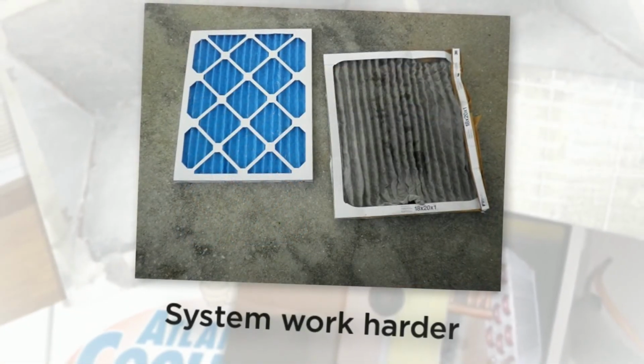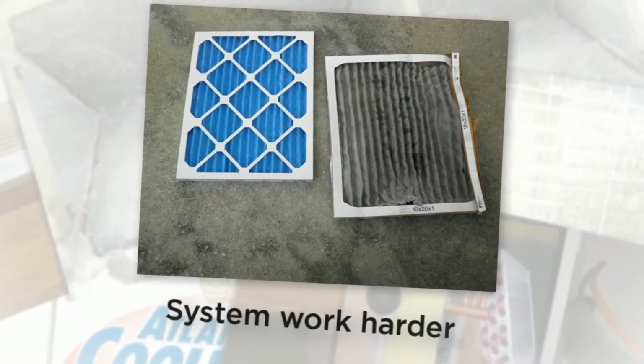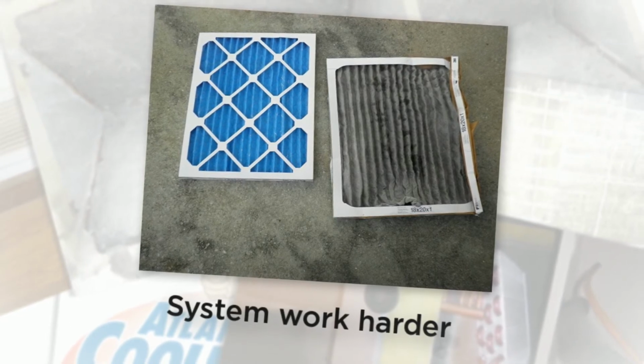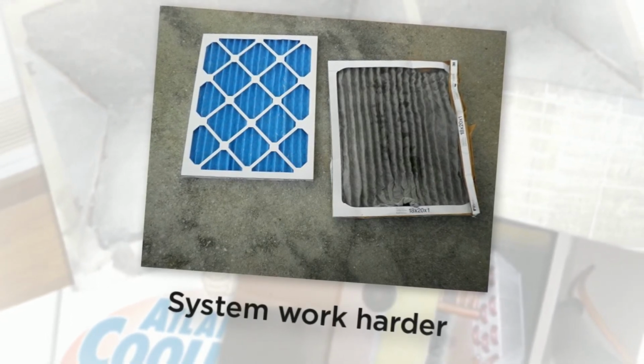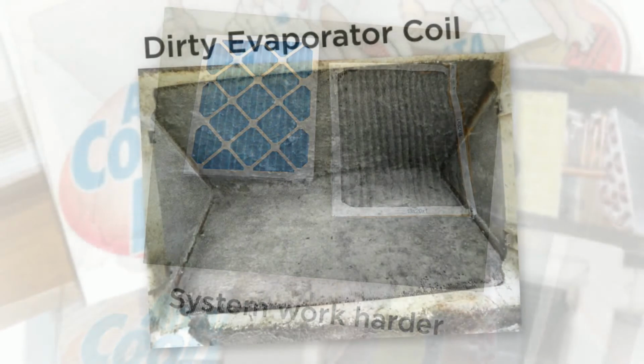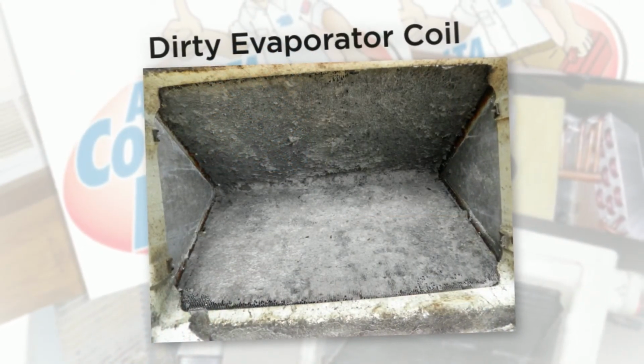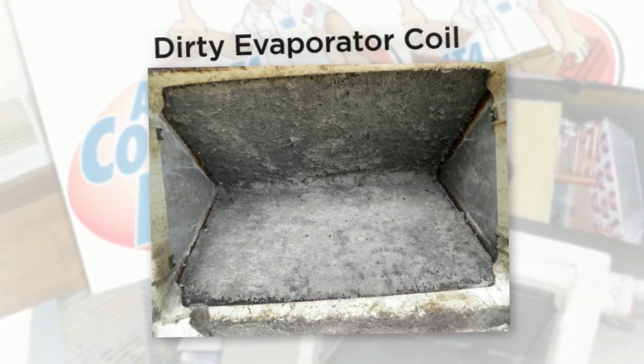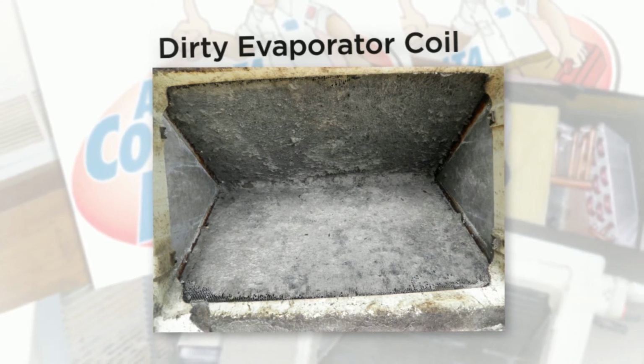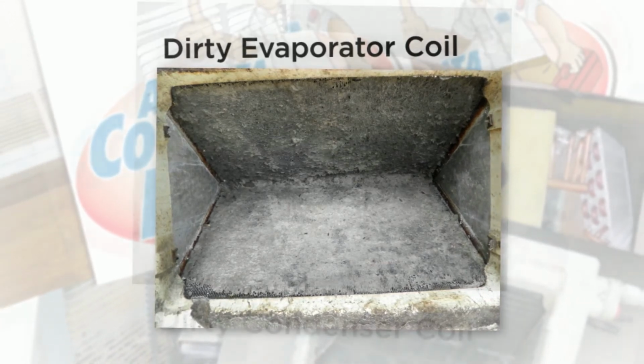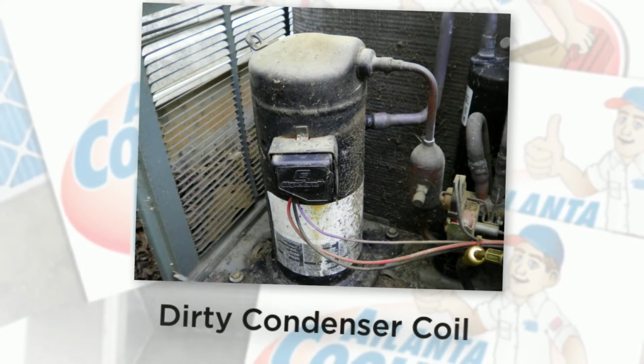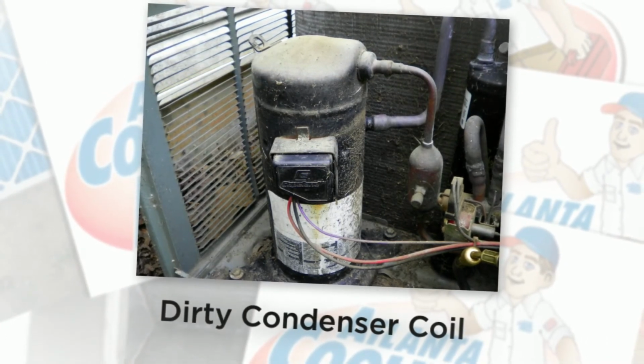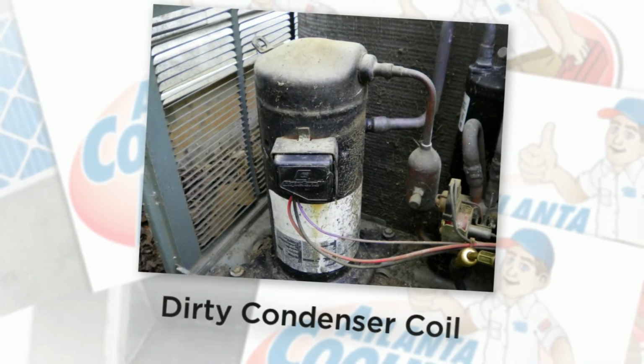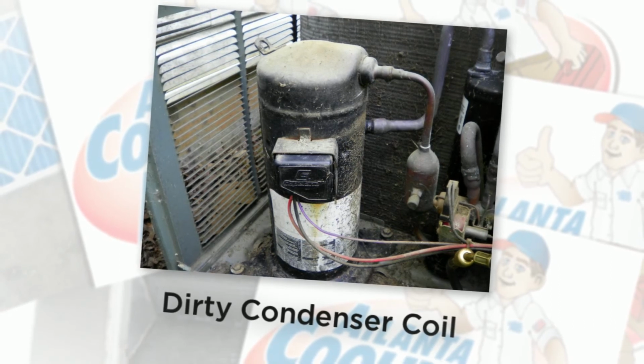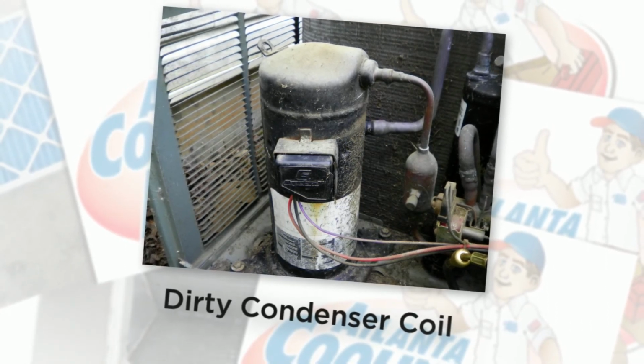If the evaporator coil is dirty, the system will not have the ability to pick up the proper amount of airflow across the coil, causing the system to not cool properly. This also affects the evaporator coil, blower motor, and compressor. If the condenser coil is dirty, the system cannot discharge the heat properly. Again, this will cause undue stress on the system. All three of these scenarios can lead to the system freezing up and can also create a leak within the refrigerant system.